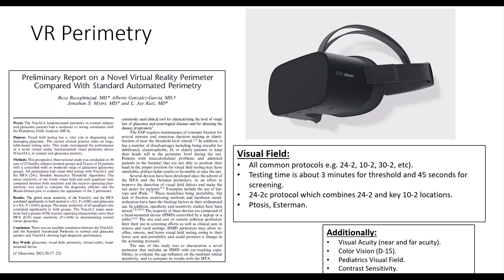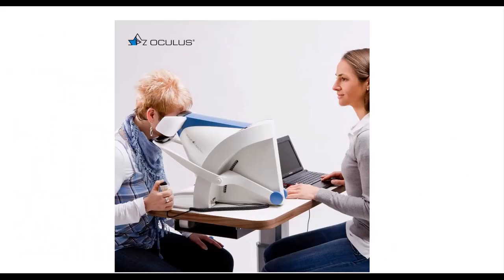Right now, headset devices are an adjunct — a nice thing to have for some situations. Personally, I don't see them replacing my tabletop devices anytime in the near future. The best choice for eye care practitioners who need to screen for disease or do threshold testing for further evaluation of glaucoma disease is an ergonomic tabletop device that has all the right bells and whistles and meets the needs of the practice.